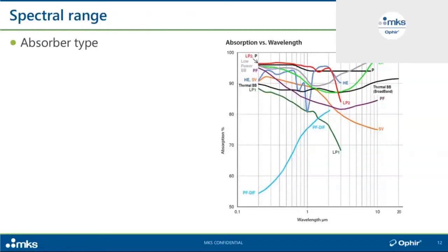Another consideration is the absorber type and spectral range. Different absorber materials absorb different wavelengths differently — some are broadband, some are not. Here you see graphs from Ophir's catalog showing all the different absorber types and their spectral curves. The actual numerical data behind these curves is available as Excel tables — feel free to ask if you need any of it.